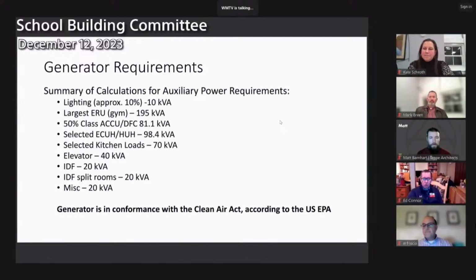There you go, Kevin, you're all set. So this is a summary of the loads, more or less replicating what Kate had gone through across the various areas - lighting and equipment on the generator - totaling just under 560 kVA, a bit under the 750 kVA capacity generator. The generator itself is 600 kW with a 750 kVA rating. As with any equipment sizing, we don't load to absolute 100% as good practice. The generator is also in conformance with the Clean Air Act according to the US EPA, which we'll see documented in a further slide.